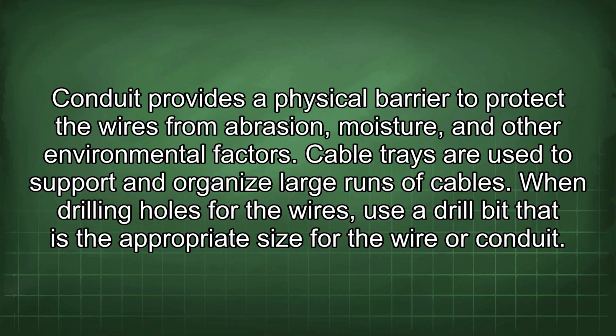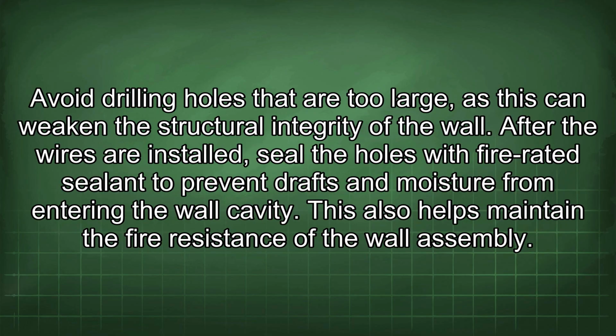When drilling holes for the wires, use a drill bit that is the appropriate size for the wire or conduit. Avoid drilling holes that are too large, as this can weaken the structural integrity of the wall. After the wires are installed, seal the holes with fire-rated sealant to prevent drafts and moisture from entering the wall cavity. This also helps maintain the fire resistance of the wall assembly.